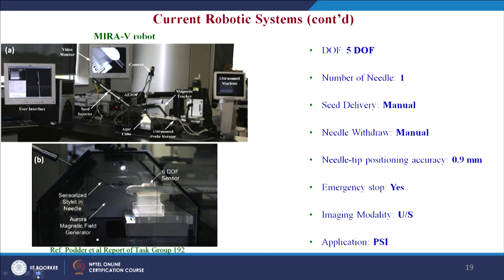The MIRA 5 system, developed by the University of Western Ontario, Canada, stands for Minimally Invasive Robot Assistant for Image-guided Lung Brachytherapy. It is a 5-degrees-of-freedom system with manual seed delivery and needle withdrawal. Needle tip positioning accuracy is 0.9 mm. It is equipped with an emergency stop and is used for seed implantation.